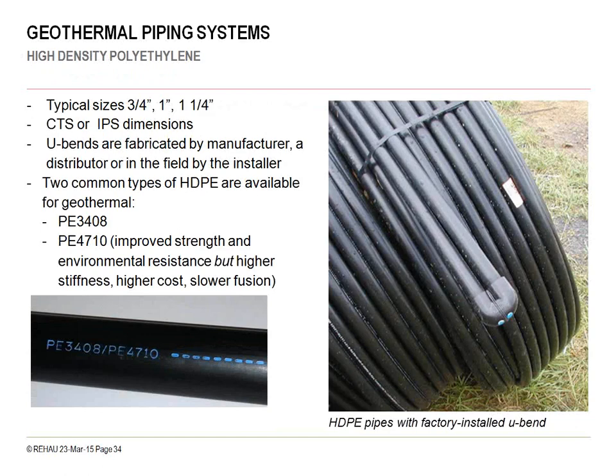Some of the sizes for typical heat exchange pipe are 3/4 inch, 1 inch, 1.25 inch. Generally it's in IPS dimensions, iron pipe size. The U-bends are fused and welded in at the factory where the pipe is made, fabricated in a factory setting, not out in the field. You can see that fused U-bend at the bottom of the loop on the Hdpe coil on the right.